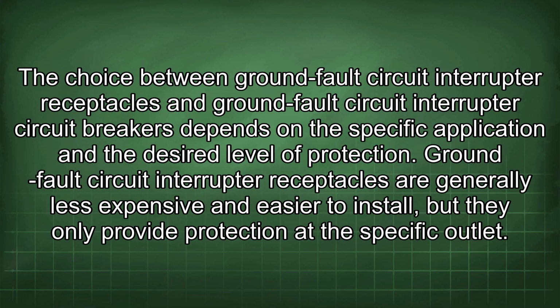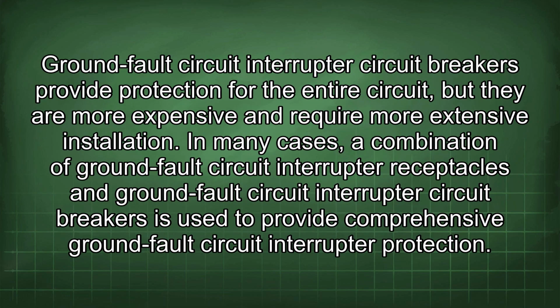The choice between ground fault circuit interrupter receptacles and ground fault circuit interrupter circuit breakers depends on the specific application and the desired level of protection. Ground fault circuit interrupter receptacles are generally less expensive and easier to install, but they only provide protection at the specific outlet. Ground fault circuit interrupter circuit breakers provide protection for the entire circuit, but they are more expensive and require more extensive installation. In many cases, a combination of ground fault circuit interrupter receptacles and ground fault circuit interrupter circuit breakers is used to provide comprehensive ground fault circuit interrupter protection.